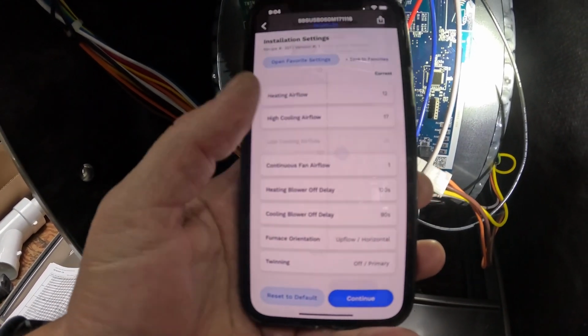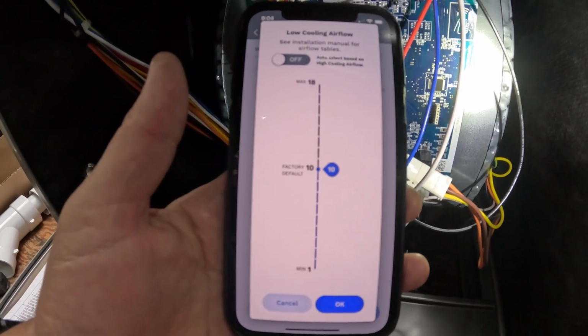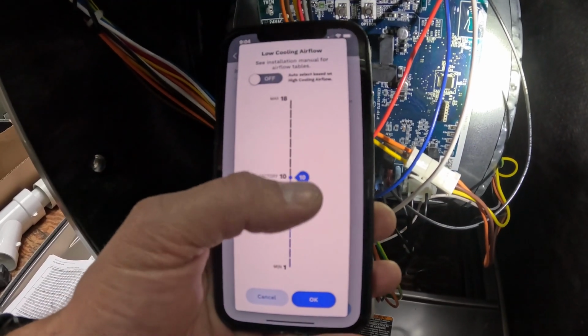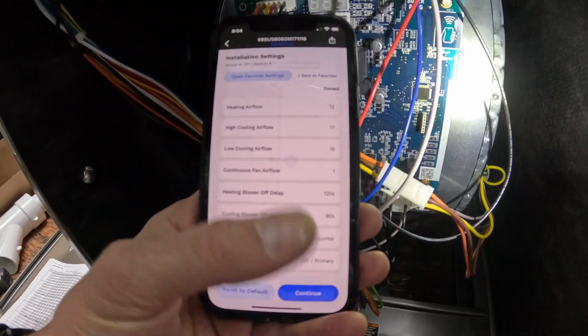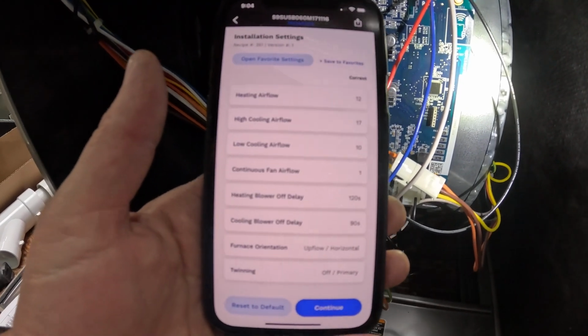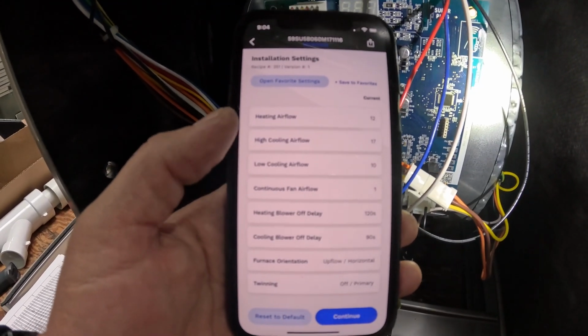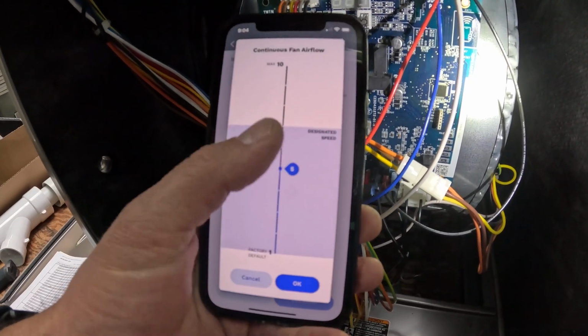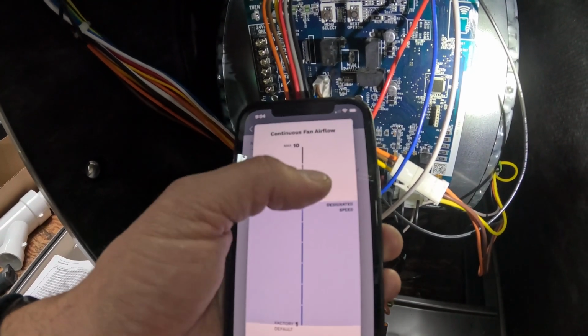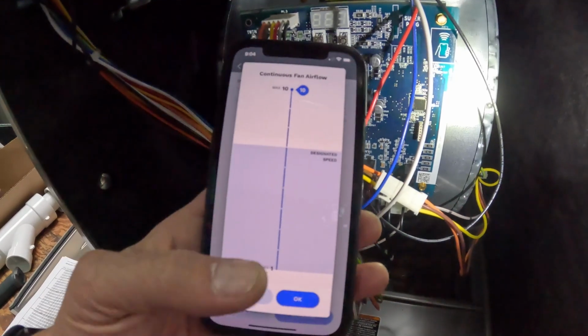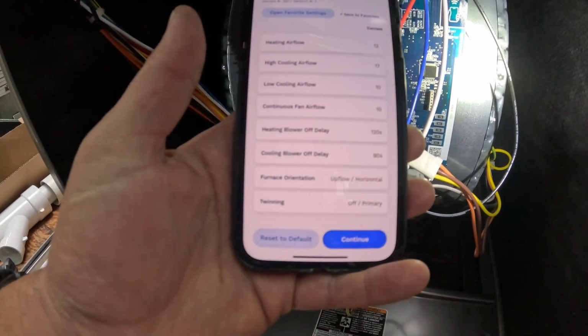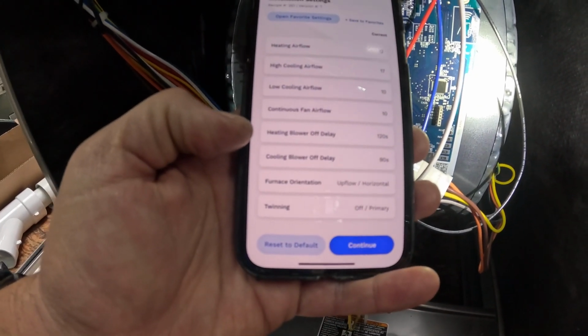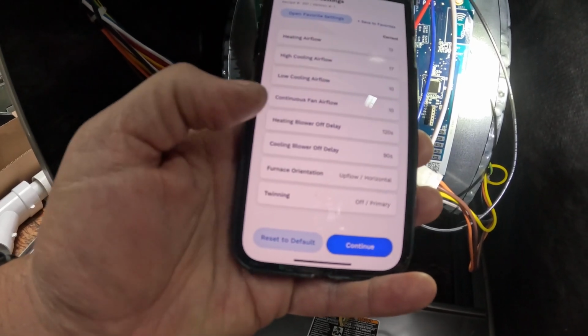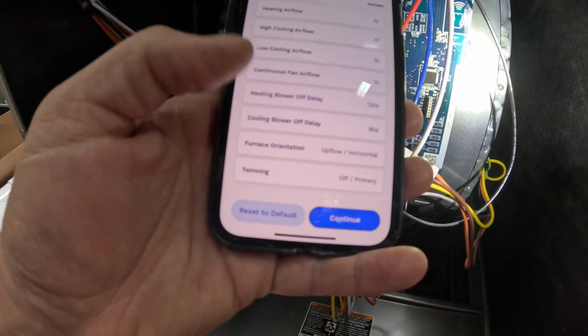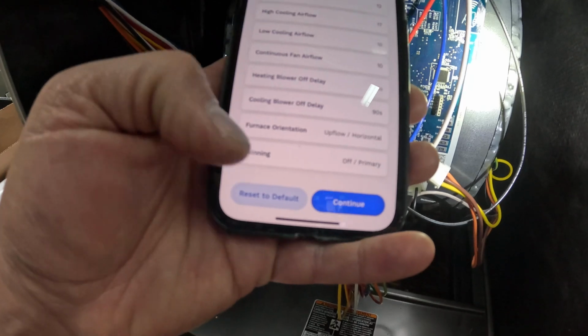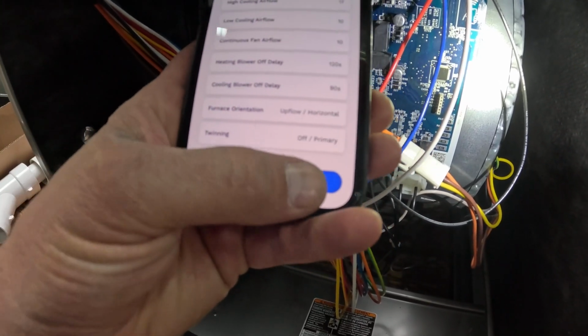The low cooling: this system potentially could have a 2-stage condenser outside. You probably leave it at the default 10, that's fine. If it's not a 2-stage condenser, if it's a single stage, it will automatically be the high cooling airflow. Continuous fan, we're going to move that all the way up to a 10. And then we're going to select OK. In here, you can also select heating blower off delay if you'd like, cooling blower off delay, and furnace orientation. We'll just consider it an upflow or horizontal, and we're not doing any twinning. So we're going to continue.